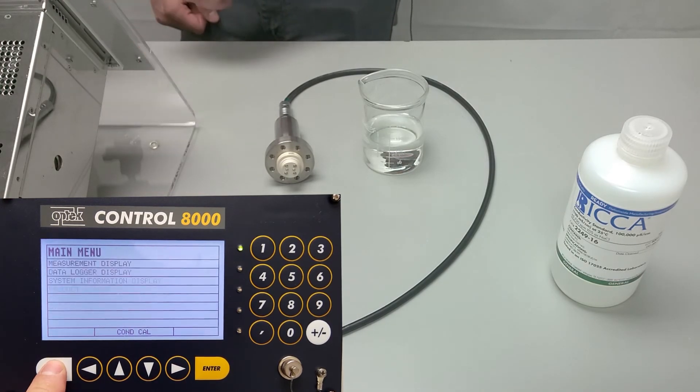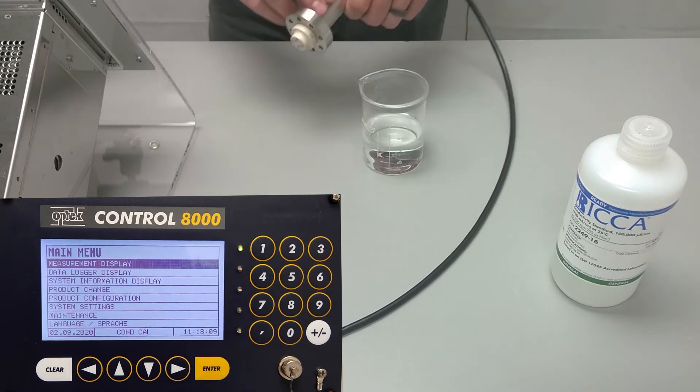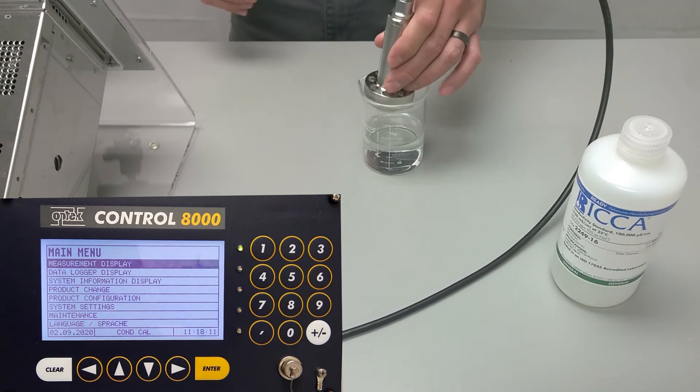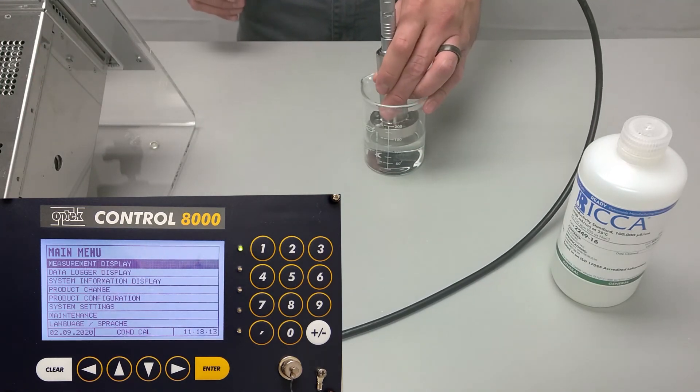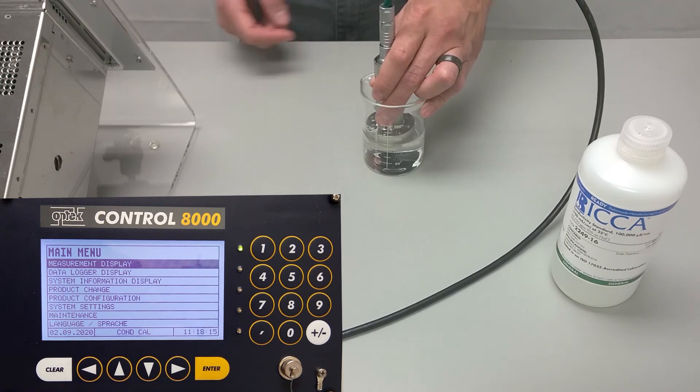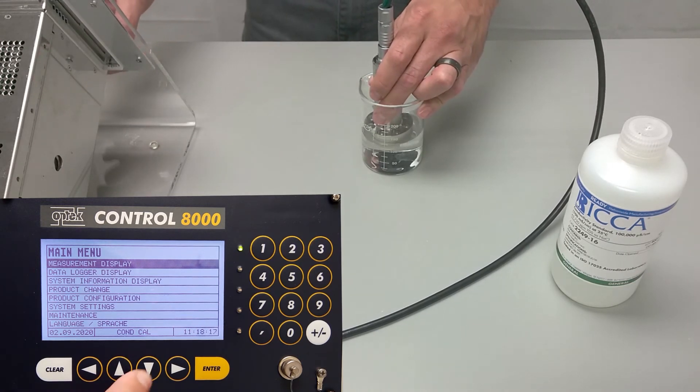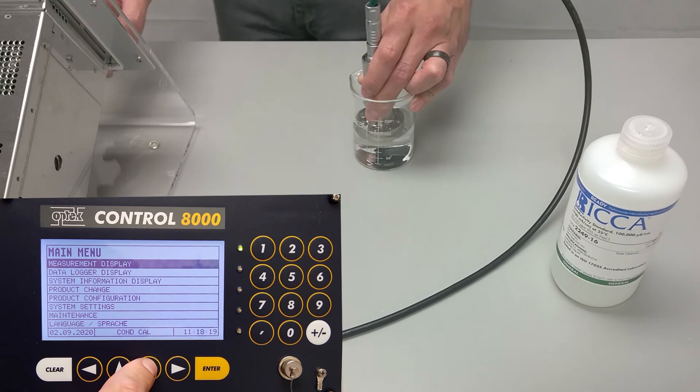Press clear to get back to that main menu, and now we'll start the calibration portion. We'll introduce our conductivity sensor to our solution and ensure that we have at least an inch of space between the bottom of the beaker and the probe so that we don't have any wall effects.